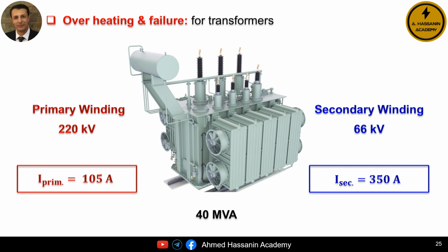Supposedly, there should be no obvious reason for the temperature rise. So, what is one of the possible causes of this problem? Without a doubt, there are many faults that could lead to an increase in the temperature of the transformer, and one of the most important is the phenomenon of the skin effect.